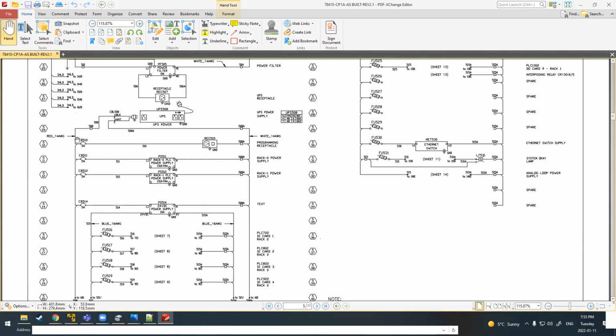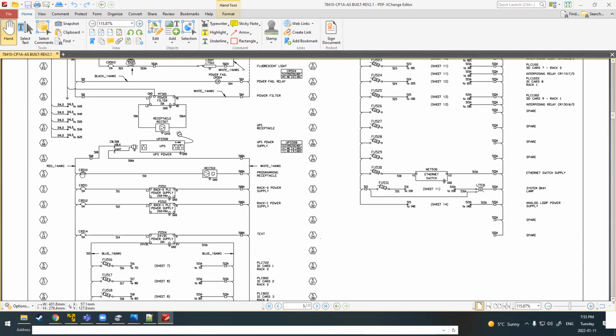So when you look at these drawings, you would want to read from left to right, because if these circuit breakers are open, then this, I'm going to do this in green. So power, in theory, will come down. If this circuit breaker is closed, we'll go through. This receptacle will have power, and now you'll have a load. So you could plug your laptop into this receptacle and you'll have power. If it comes down here and this receptacle is closed, that will complete the circuit. This power supply will turn on and your processor will turn on and your second power supply will turn on. And then this will go back up to neutral and this will complete that circuit.